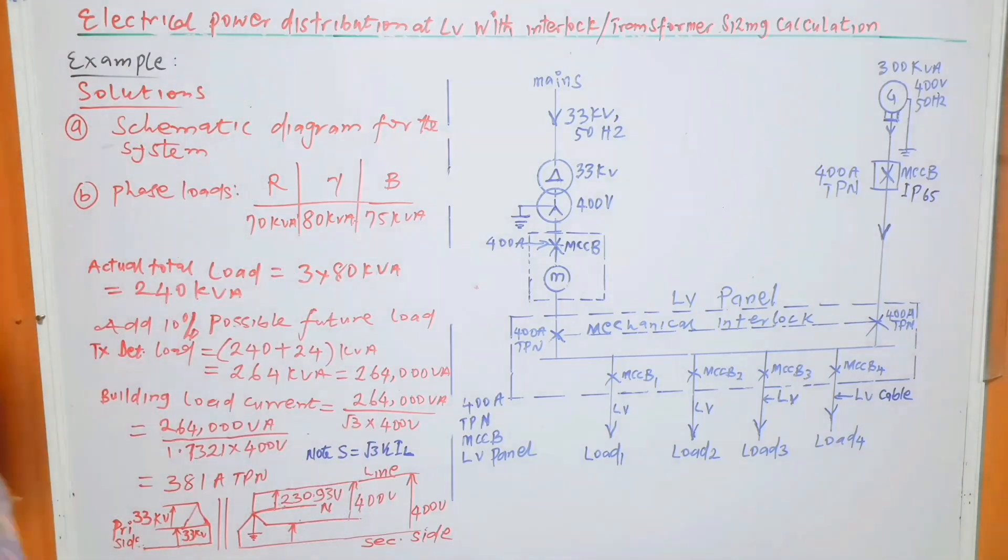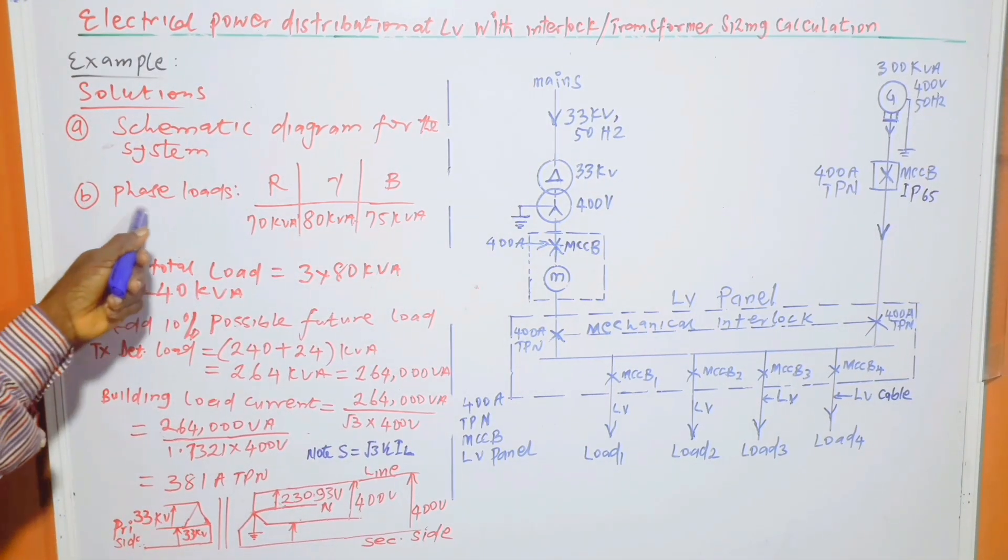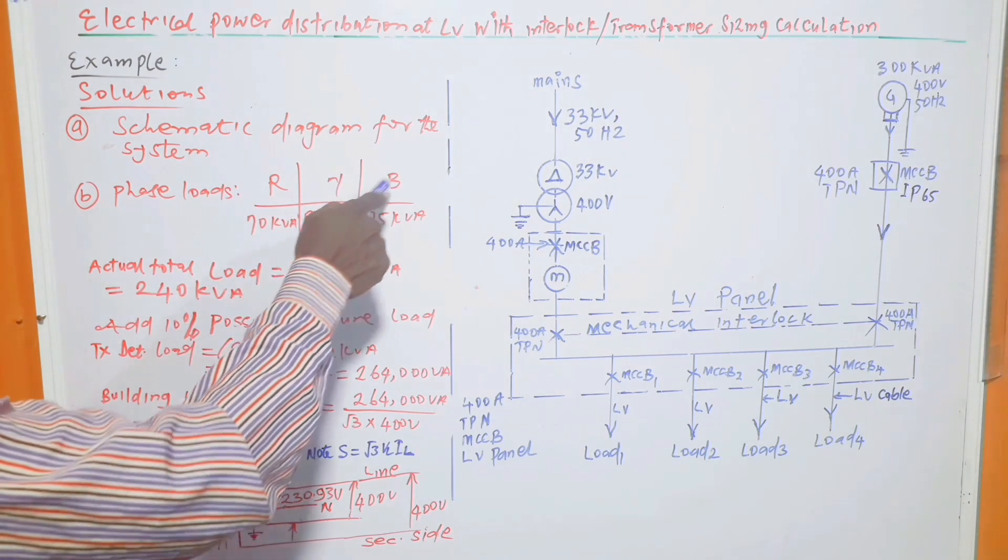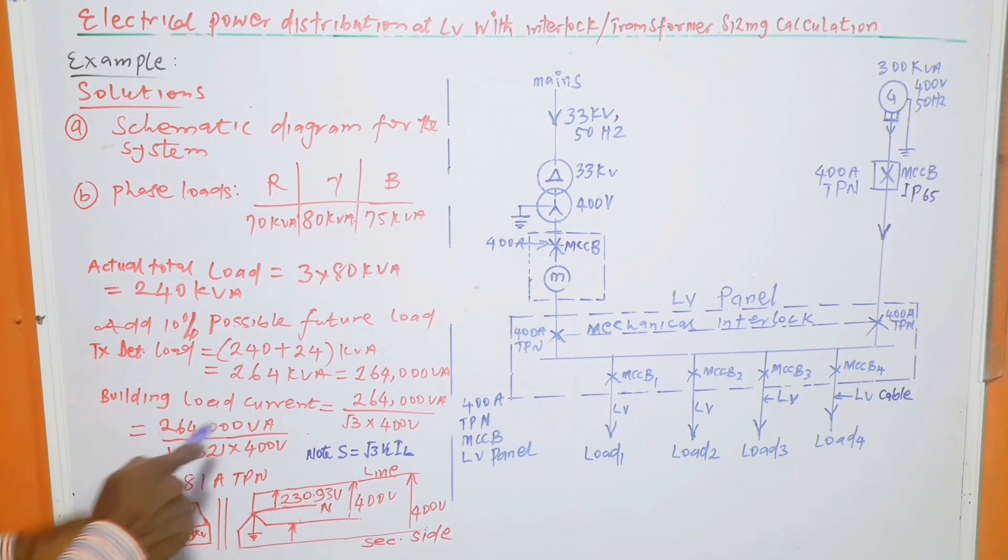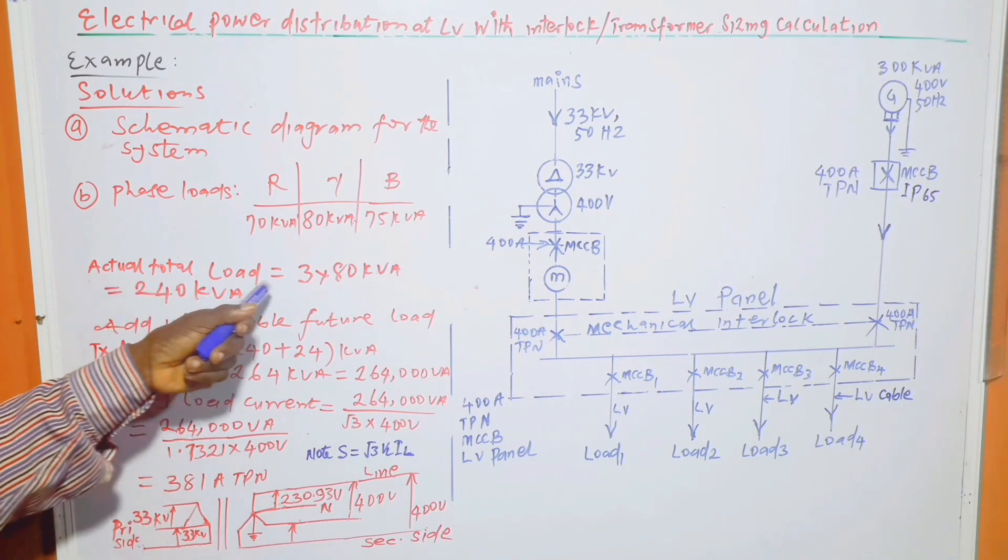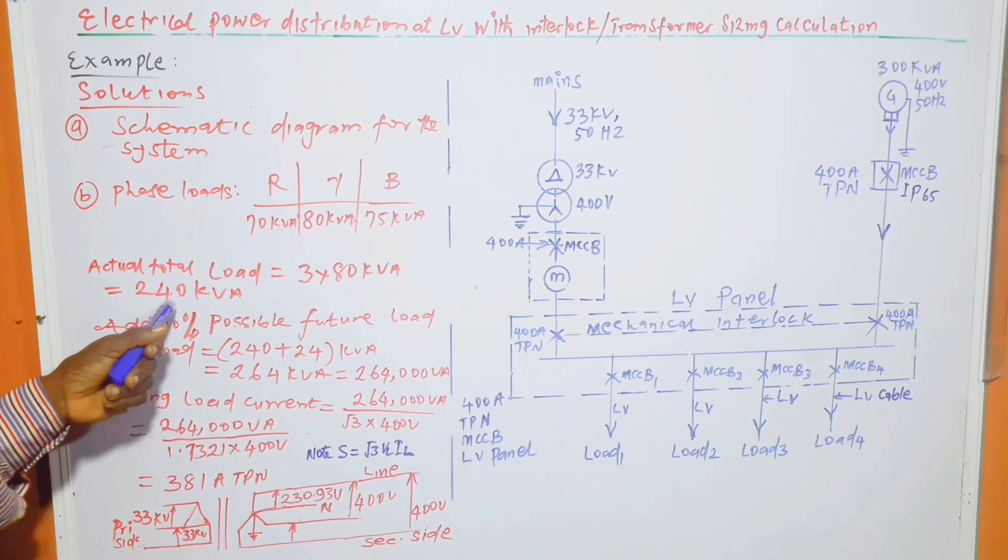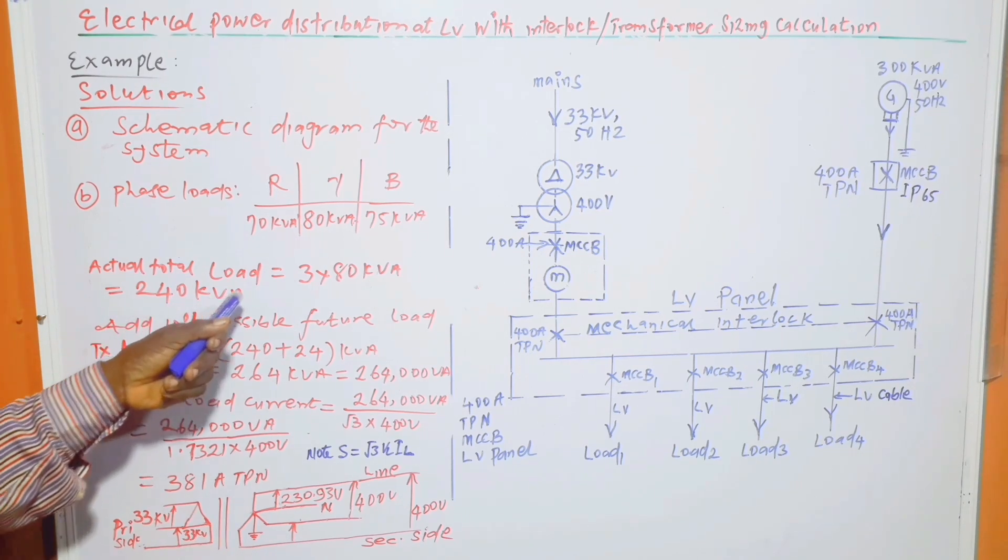Now, B part, phase loads: red phase 70 kVA, yellow phase 80 kVA, blue phase 75 kVA. Actual load is equal to 3 times 80 kVA, which is equal to 240 kVA.